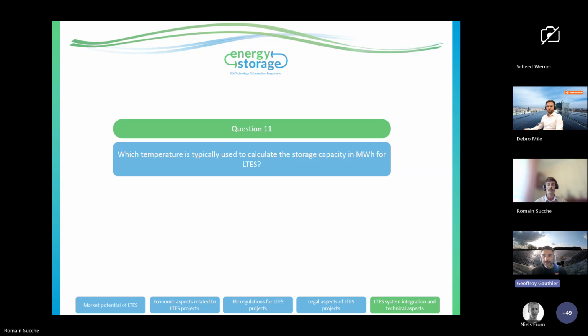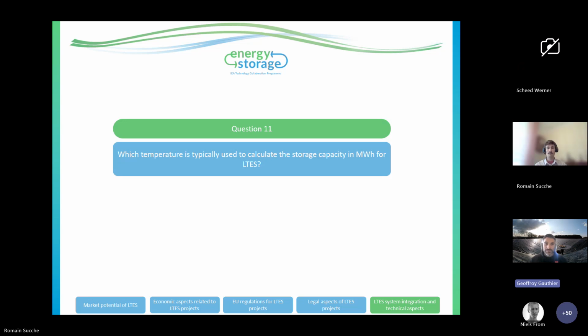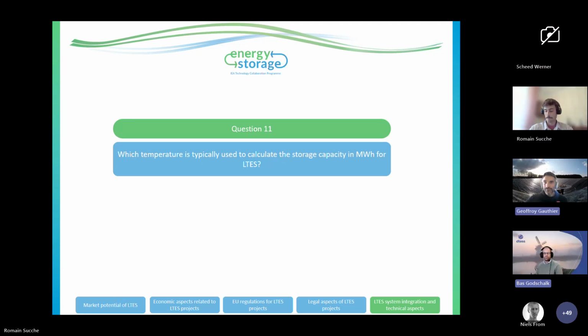And if you're coupled directly to your district heating network, then it's the return temperature of that network. But as Niels mentioned, if you're coupling it with a heat pump, you can go below this temperature, even lower. Typically for a district heating network in Denmark it would be 90 to 45-50 degrees for a PTES, and for a TTES it would be 95-97 to 45-50. That's the typical range.